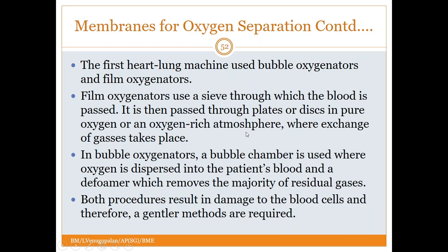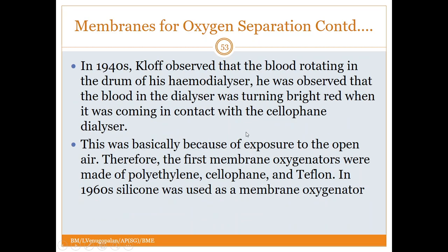In the bubble oxygenator, a bubble chamber is used where the oxygen is dispersed within the chamber. It's an oxygen-rich chamber, and when blood passes through the chamber, the oxygen would diffuse into the blood, and there's a defoamer which would remove the majority of the residual gases such as carbon dioxide. However, both these procedures are not very kind to the RBC and the blood, right? So there's quite a lot of cell damage occurring, and therefore a gentler method was required.